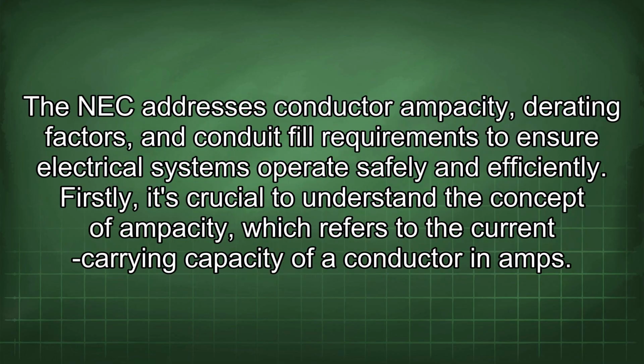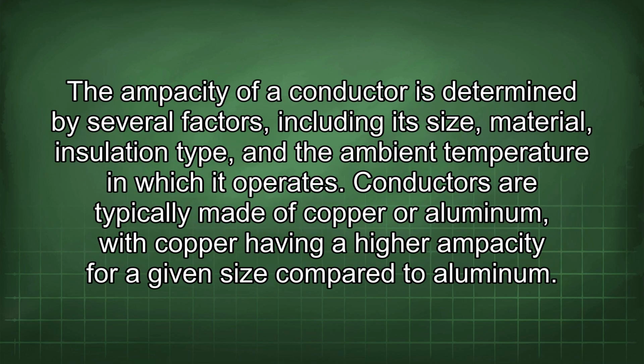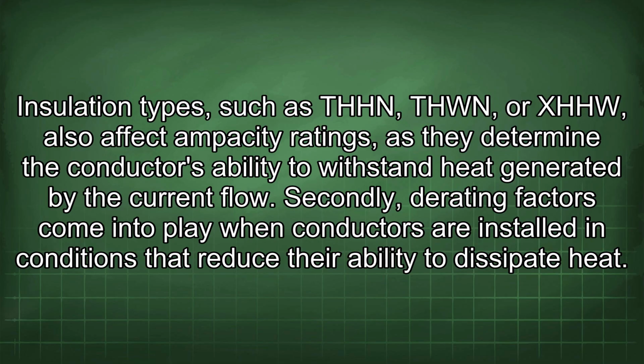The NEC addresses conductor ampacity, derating factors, and conduit fill requirements to ensure electrical systems operate safely and efficiently. Firstly, it's crucial to understand the concept of ampacity, which refers to the current carrying capacity of a conductor in amps. The ampacity of a conductor is determined by several factors, including its size, material, insulation type, and the ambient temperature in which it operates. Conductors are typically made of copper or aluminum, with copper having a higher ampacity for a given size compared to aluminum. Insulation types, such as THHN, THWN, or XHHW, also affect ampacity ratings, as they determine the conductor's ability to withstand heat generated by the current flow.